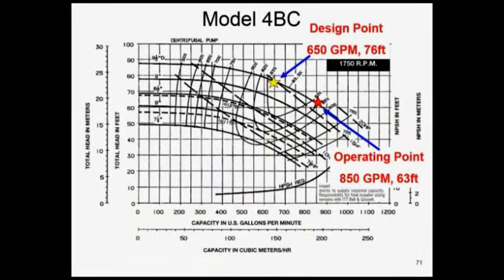But let's go to a model again. First of all, the yellow star is an impeller size of 9.5 inches. That's what you specified. That's what the engineer had. And that's supposed to be 650 GPM at 76 feet of head. Fantastic. But you had a complaint of noise, and you asked for the differential pressure across the pump. Now, you can't change that impeller size. And right now, let's have a fixed speed. Let's not play the speed game yet. We can bring that in later. Be happy to, but not yet. We're going to be at constant speed at the point we are right now.